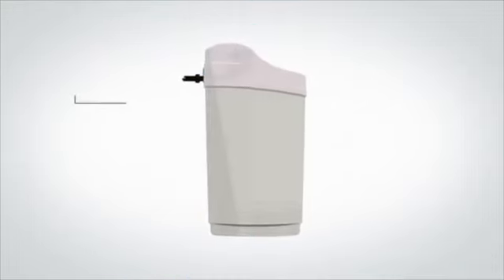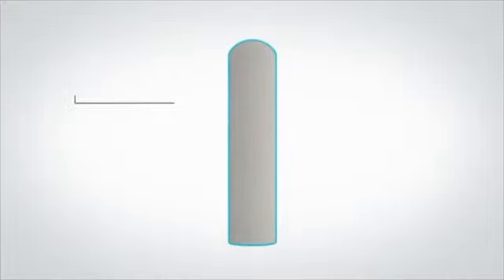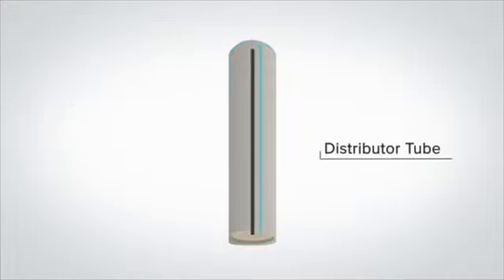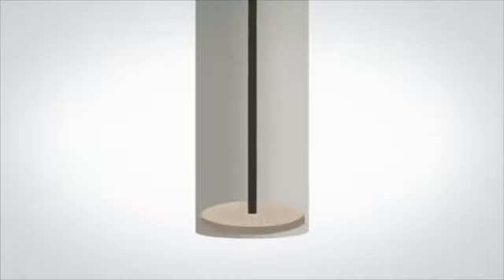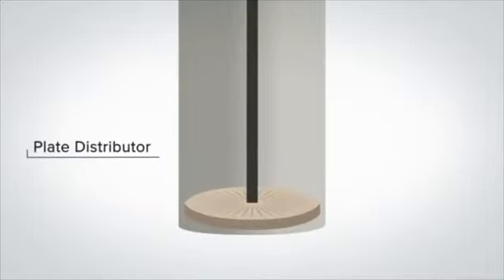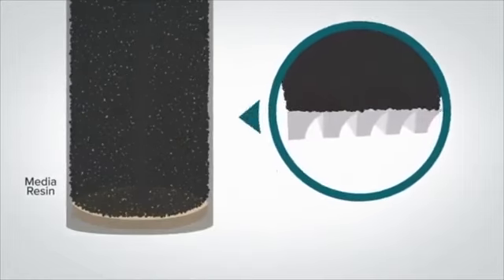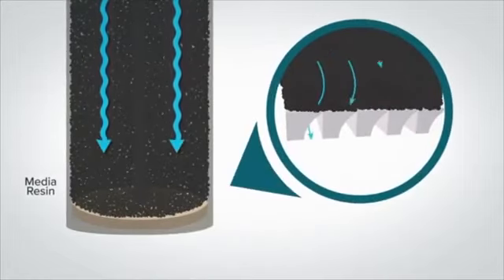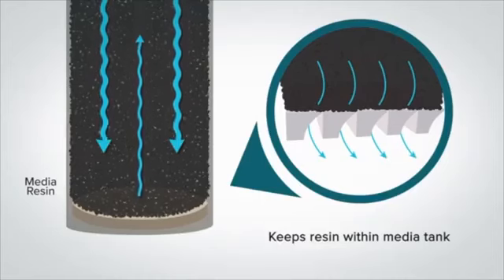Under the control valve is the media tank. Inside the media tank is a tube that runs to the bottom of the tank called the distributor tube. At the bottom of the distributor tube is an innovative plate distributor. The plate distributor has many small slits that allow the clean water to enter the distributor tube but keeps the resin from entering the home water supply.